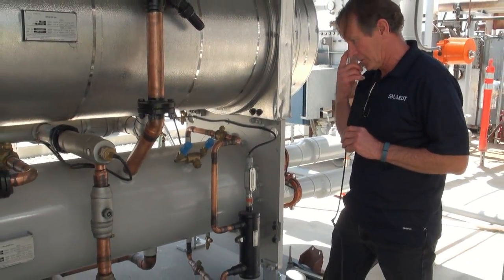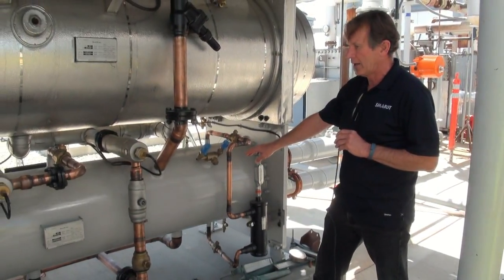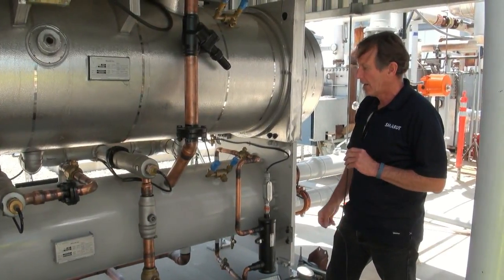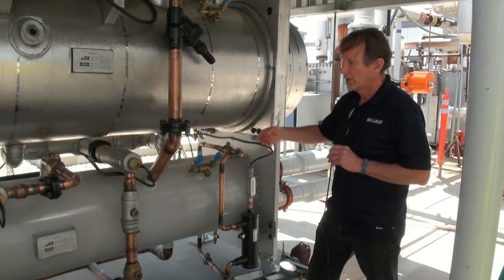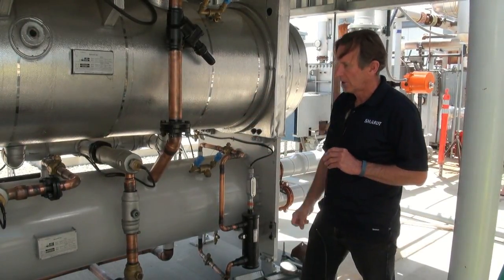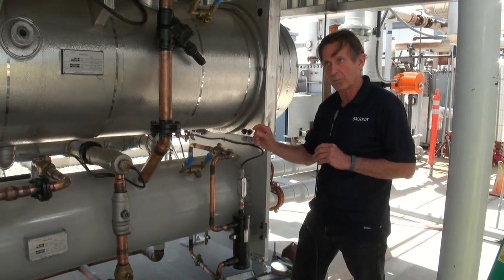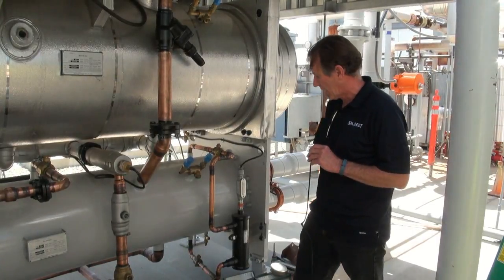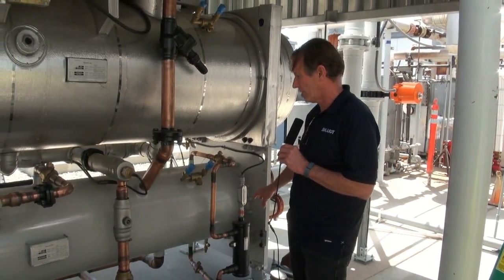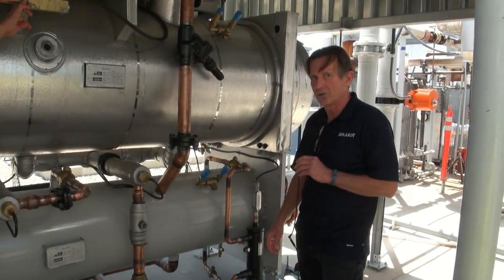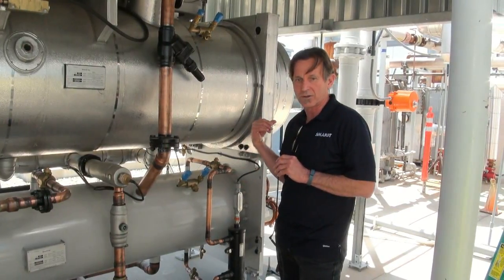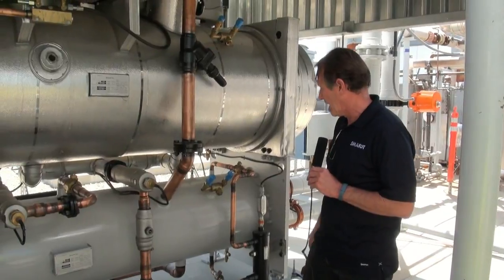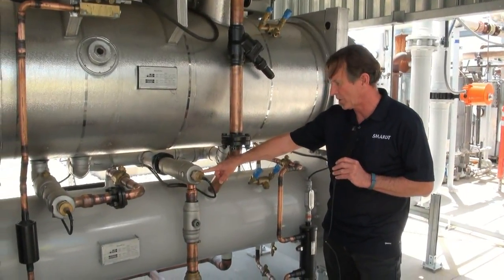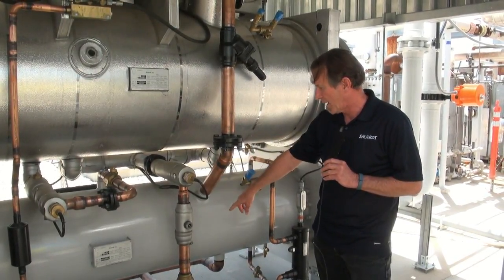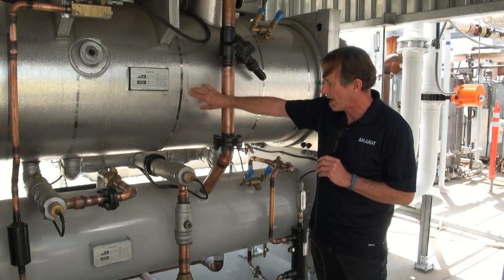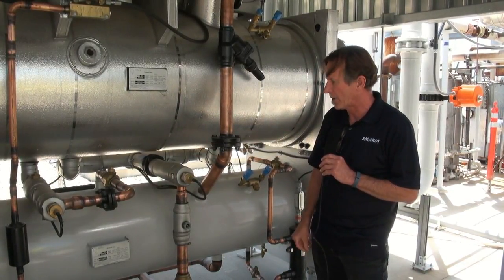Basically, this machine is looking at level in the condenser, and it'll open or close the expansion valve. If the level's too high, it'll open and empty some of that liquid into the evaporator. If the level's too low, it'll pinch down and stack more liquid in the condenser. So that sensor is feedback to the controller, and in turn the controller sends a signal to the boards that are actually operating the valves. This is the expansion valve. This is our separation between the high side and low side. We're taking high pressure refrigerant and expanding it across this valve into the low pressure side, and that's where we develop our evaporation and cooling.